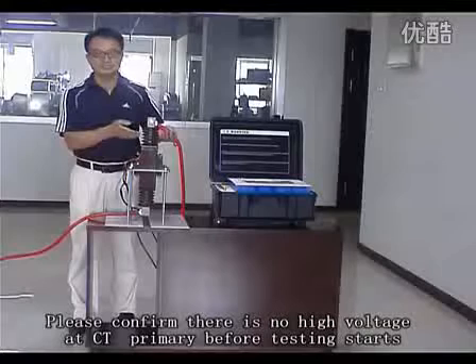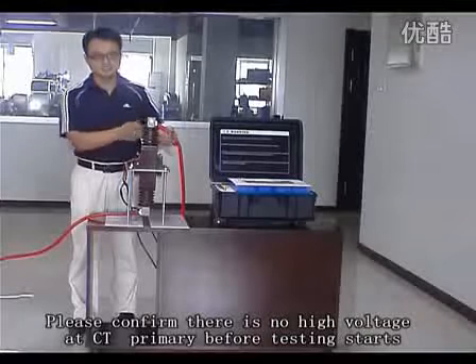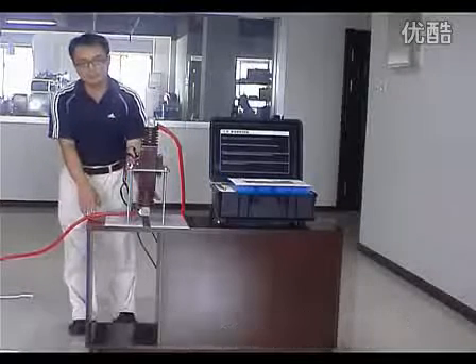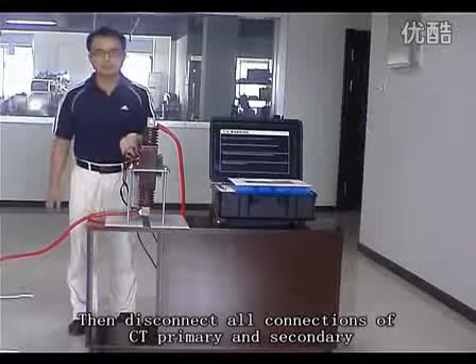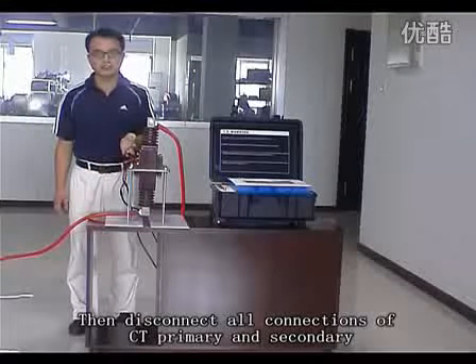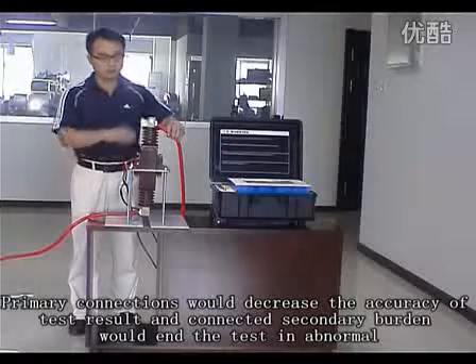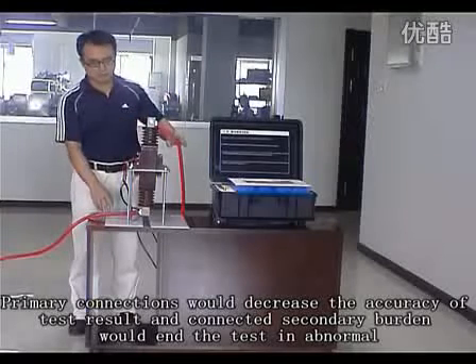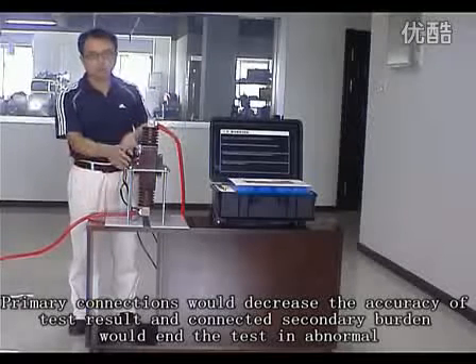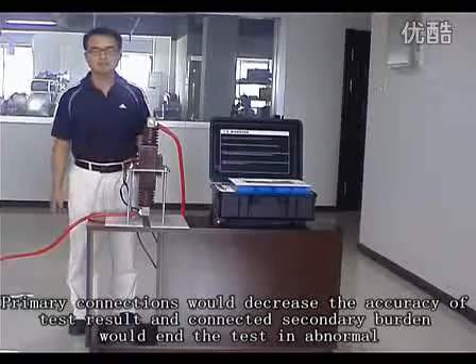Please confirm there is no high voltage at the CT primary before testing starts, then disconnect all connections of the CT primary and secondary. Primary connections would decrease the accuracy of test results, and a connected secondary burden would end the test abnormally.